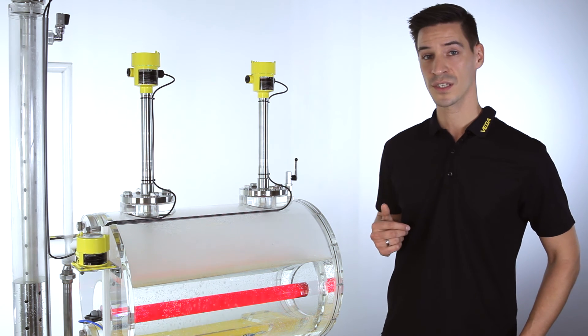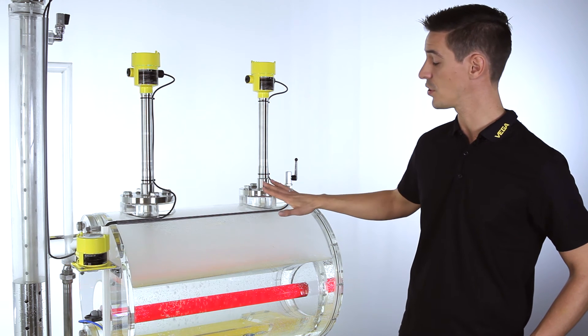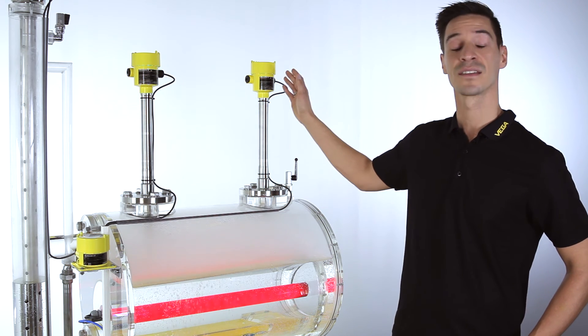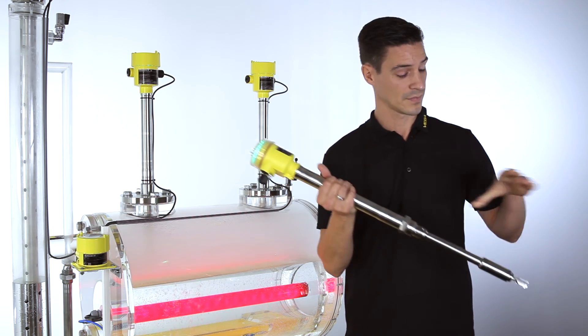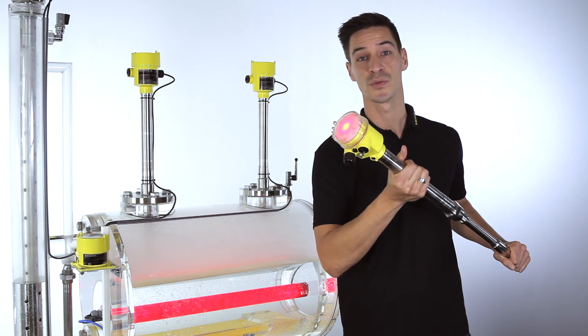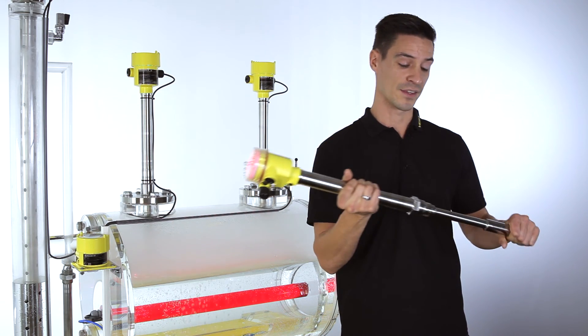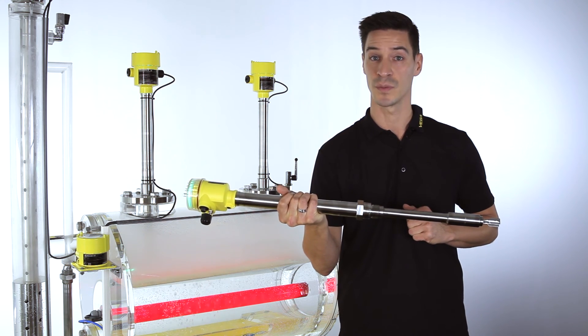The VegaSwing 66 requires no adjustment. You just have to install it and realize the electrical connection. As soon as the level covers the fork, a switching signal will be created. Thanks to the version with tube extension, it is possible to detect levels up to three meters.